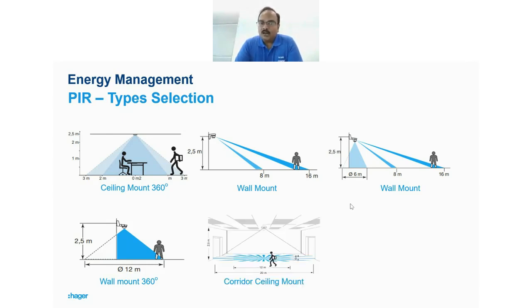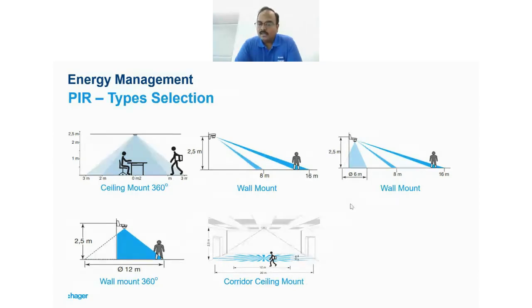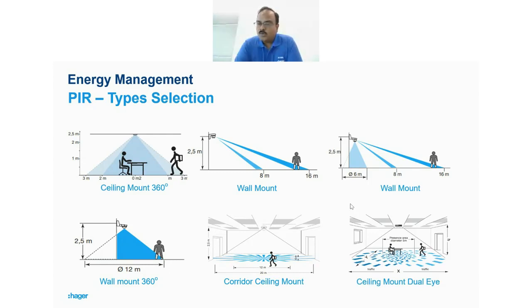Another important type is the corridor detection pattern — a rectangular detection area, typically 4 meters by 20 meters, suited to a corridor's shape. A 360-degree ceiling-mount corridor motion detector can achieve this. There are also dual-eye detectors, which contain two sensors at an angle inside one unit to cover a longer combined distance. These types cover approximately 90–95% of detection zone requirements.